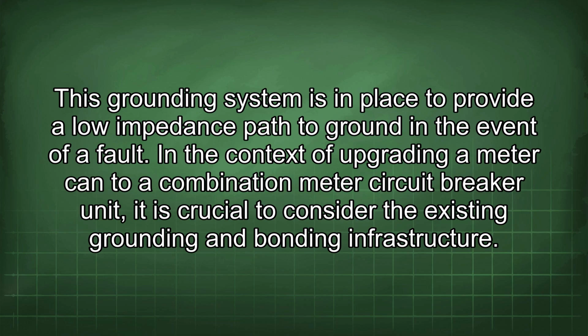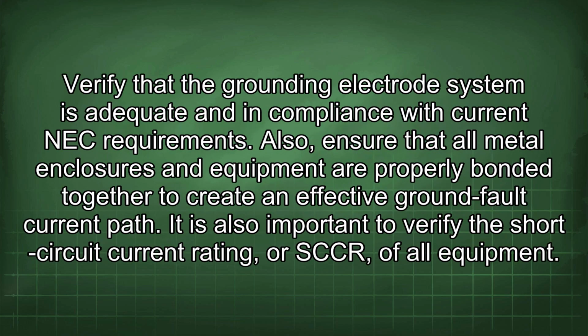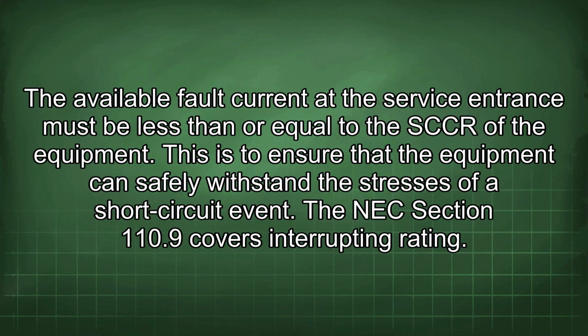In the context of upgrading a meter can to a combination meter circuit breaker unit, it is crucial to consider the existing grounding and bonding infrastructure. Verify that the grounding electrode system is adequate and in compliance with current NEC requirements. Also, ensure that all metal enclosures and equipment are properly bonded together to create an effective ground fault current path. It is also important to verify the short circuit current rating, or SCCR, of all equipment. The available fault current at the service entrance must be less than or equal to the SCCR of the equipment. This is to ensure that the equipment can safely withstand the stresses of a short circuit event.